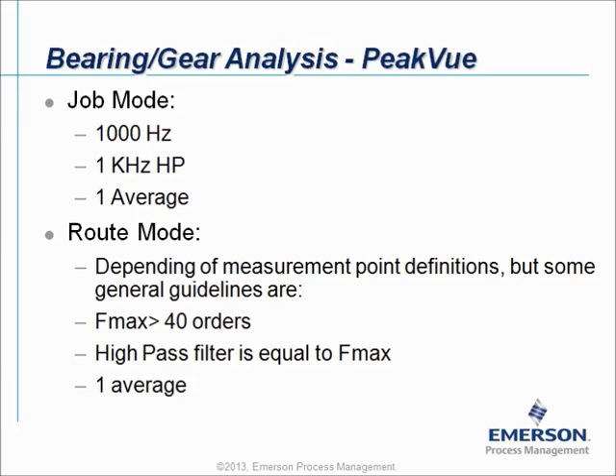PeakVue measurements can be measured in the job mode or in the route mode. If you measure peak view data in the job mode using the default settings, it will collect a spectrum up to 1000 Hz with a high pass filter of 1000 Hz and one average.